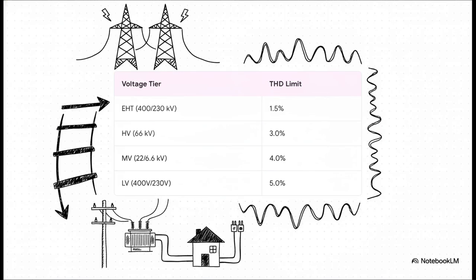And the regulations tackle that pollution with a very strict THD ladder right at the point of common coupling. It steps down tier by tier. At the extra high voltage tier, it's capped at a super restrictive 1.5%, where, by the way, odd harmonics cannot exceed 1.0%, and even harmonics are tightly capped at 0.5%. From there, the limit moves to 3.0% at 66 kilovolts, 4.0% at the 22 and 6.6 kilovolt medium voltage tiers, and finally caps out at 5.0% down at low voltage.